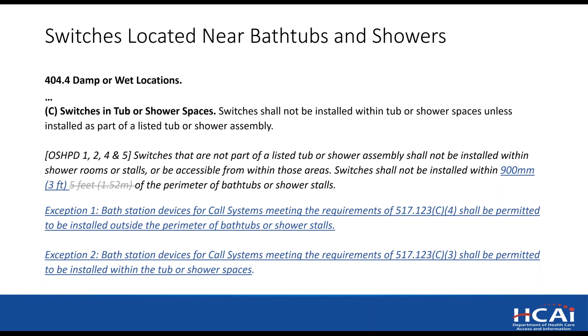And then the two exceptions are essentially allowing that nurse call can be mounted within these locations, so that the pull station at the toilet and the pull station at the showers can be installed. This matches FGI guidelines, and the requirement for these devices is to be weatherproof listed. Next slide.